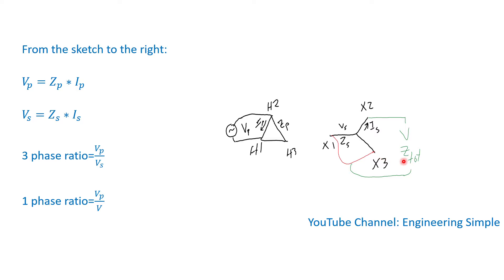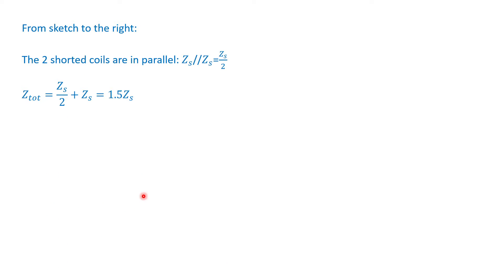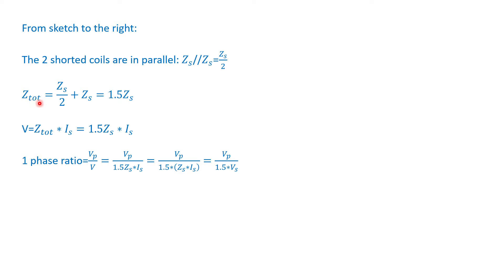With the shorted coils in parallel, the equivalent impedance of two equal parallel impedances is one half of one of them. So the total impedance is one half of the secondary impedance plus one times the secondary impedance, which equals 1.5 times the secondary impedance. From Ohm's law, the measured voltage is the total impedance times the secondary current, which is 1.5 times the secondary impedance times the secondary current. The single-phase ratio is then the primary voltage divided by this measured secondary voltage.